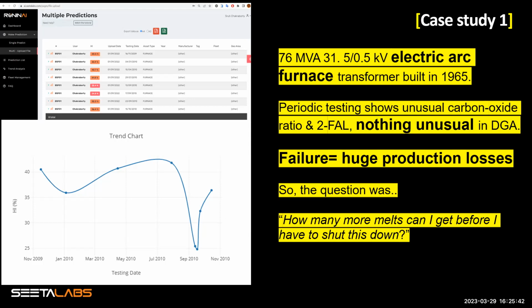This is a particular electric arc furnace transformer. I hope you all know what that is, but just for background: these are very strategic pieces of equipment, and one basic requirement of electric arc furnace transformers within the steel industry is that they are responsible for firing up the furnaces. They work under extremely high loading conditions, sometimes 1.5 load units, meaning 150% loaded.